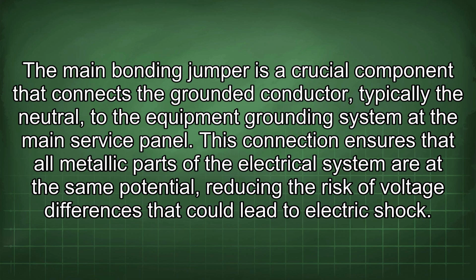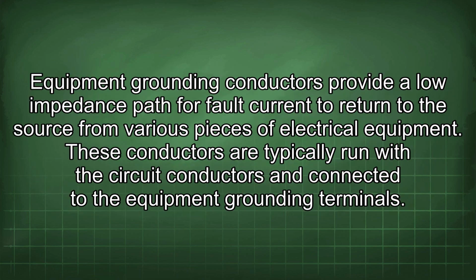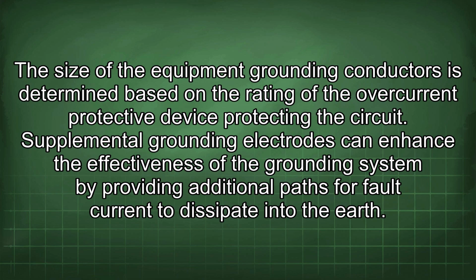This connection ensures that all metallic parts of the electrical system are at the same potential, reducing the risk of voltage differences that could lead to electric shock. Equipment grounding conductors provide a low impedance path for fault current to return to the source from various pieces of electrical equipment. These conductors are typically run with the circuit conductors and connected to the equipment grounding terminals.